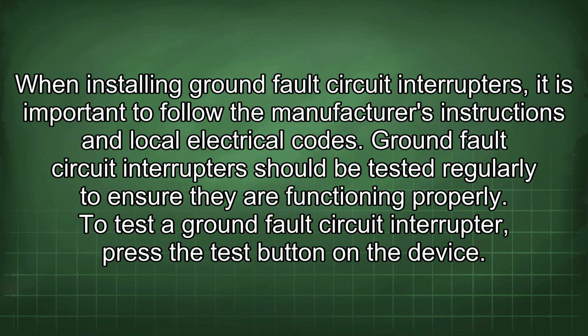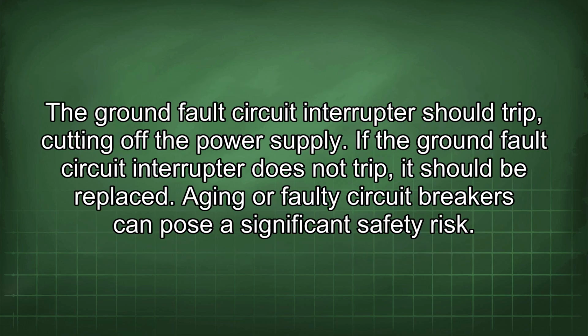When installing ground fault circuit interrupters, it is important to follow the manufacturer's instructions and local electrical codes. Ground fault circuit interrupters should be tested regularly to ensure they are functioning properly. To test a ground fault circuit interrupter, press the test button on the device. The ground fault circuit interrupter should trip, cutting off the power supply. If the ground fault circuit interrupter does not trip, it should be replaced.